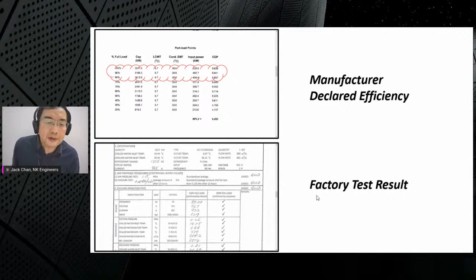If you look at this graph here, you will find that there are two distinct curves. One is the green curve. The other one is the red dots. The green curve is the efficiency declared by the supplier, rated in kilowatt per ton. So the lower the values, the more efficient it is. In other words, if the points are lower, it is more efficient; if the points are higher, it is less efficient, because you consume lower energy in your electrical system. So bear in mind, when we talk about kilowatt per ton, the lower the kilowatt per ton, the better.